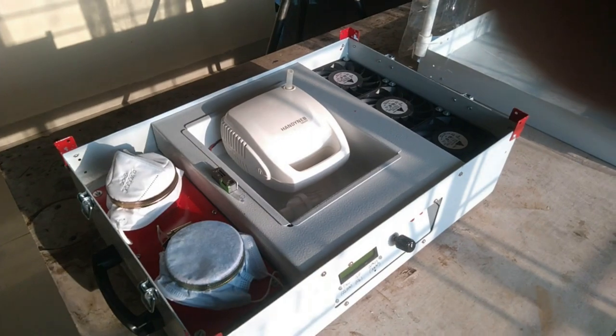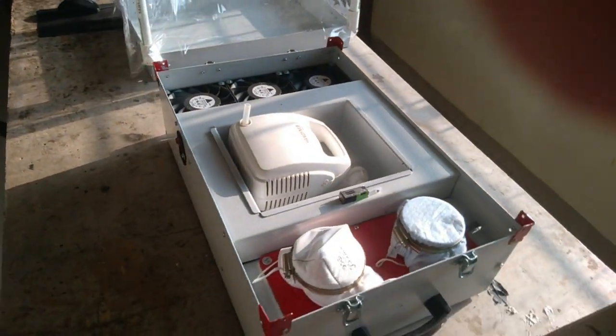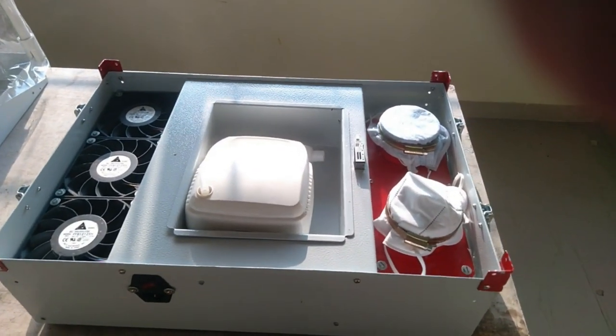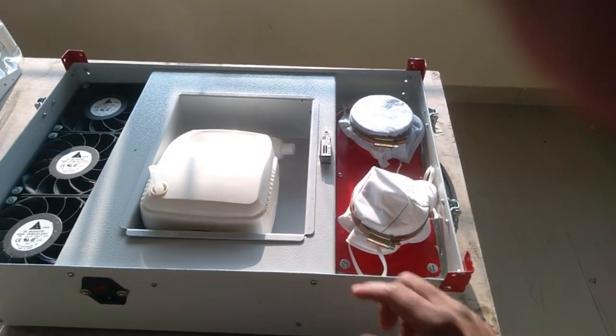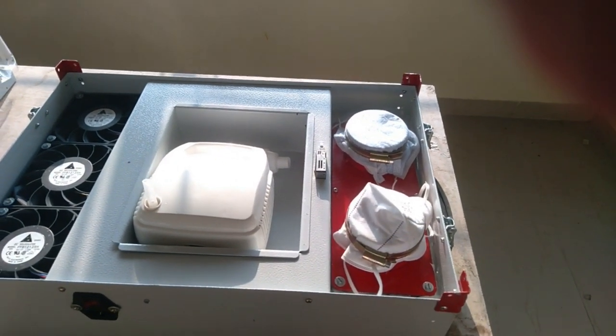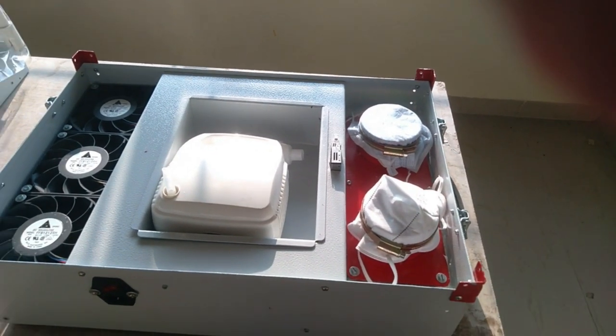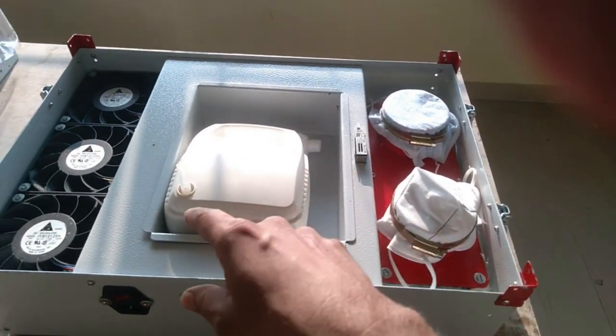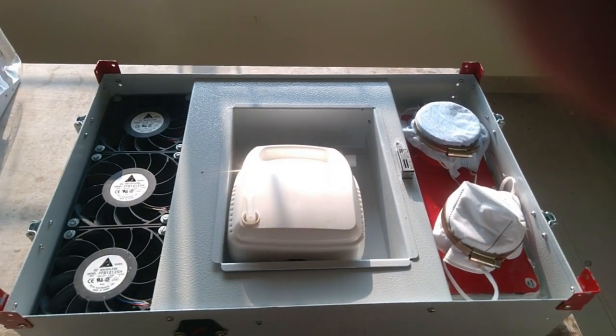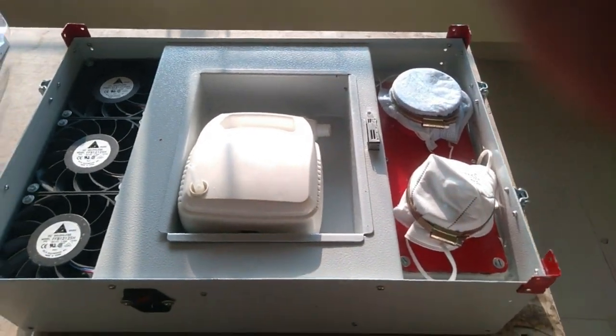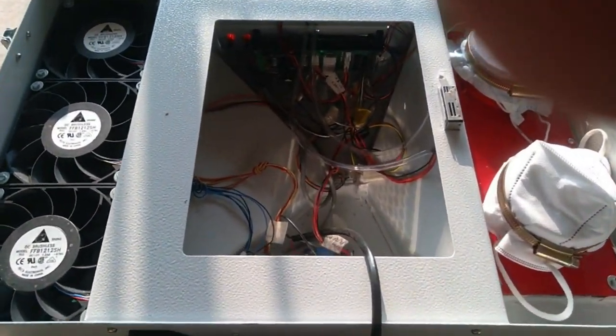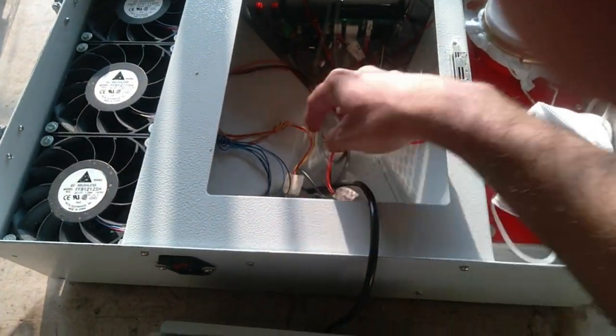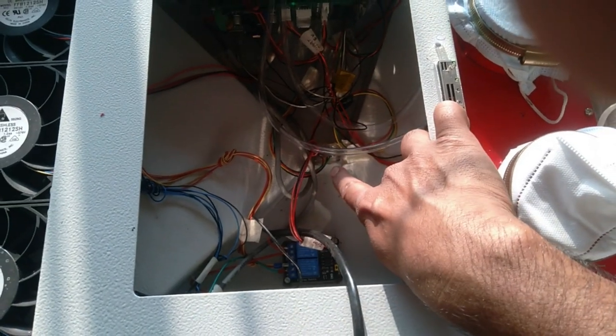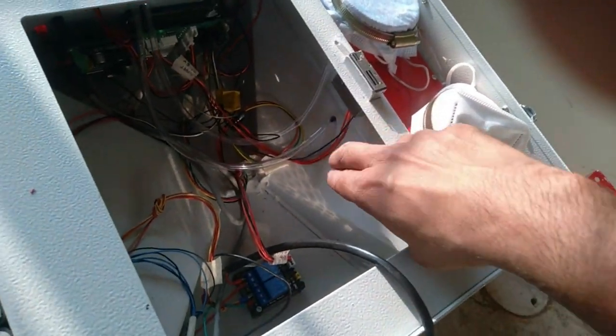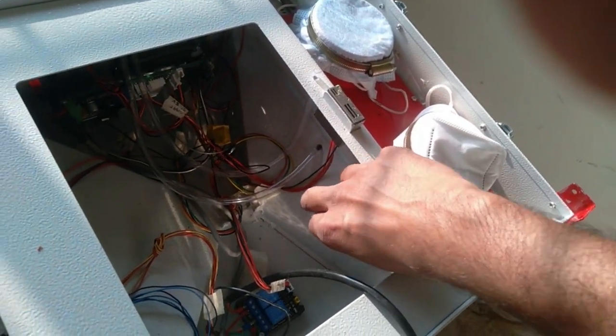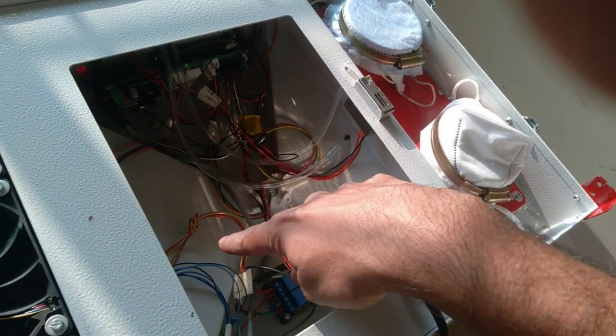This is a nebulizer, and it creates the PM 2.5 particles that are used for sensing whether the mask is working efficiently or not. This is a PM 2.5 sensor, which senses the PM 2.5 before the masks, and then inside in the chain there is another 2.5 micron sensor which detects the particles after they have passed through the mask. You can see that the fan is connected via an airflow sensor, and these two masks are connected via this conduit to the airflow sensor to this chamber.